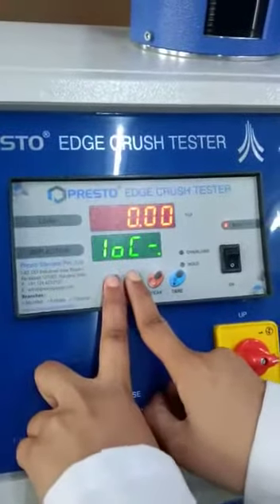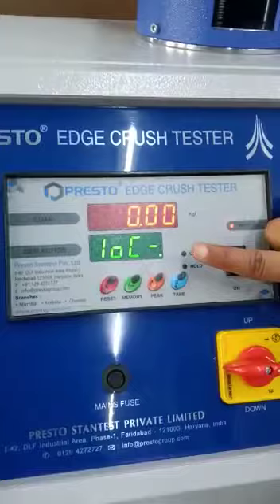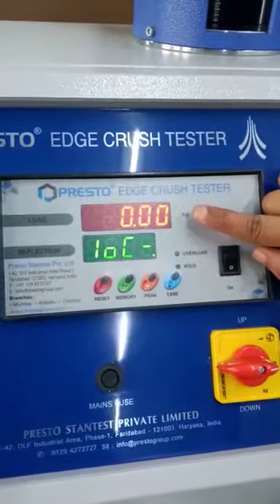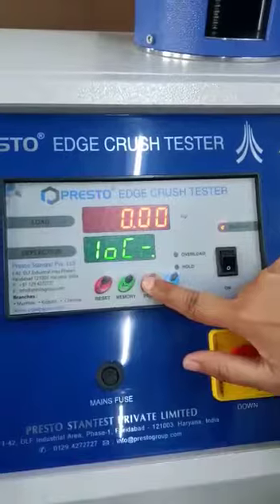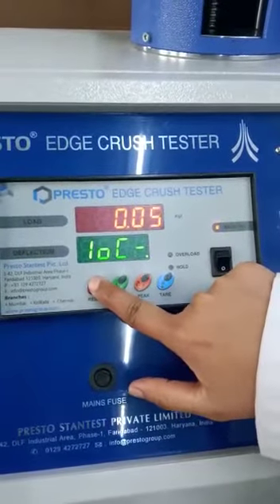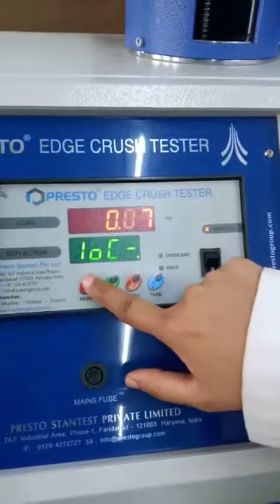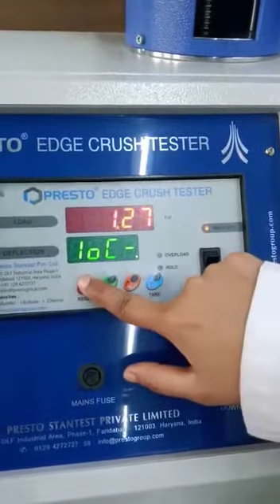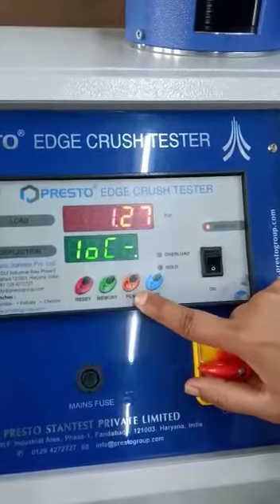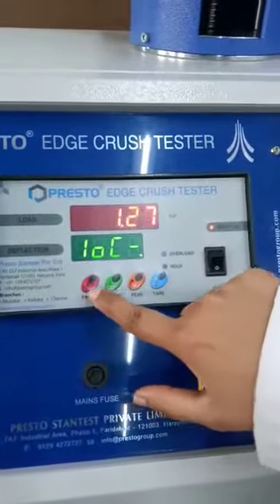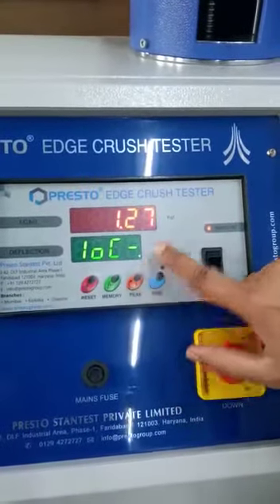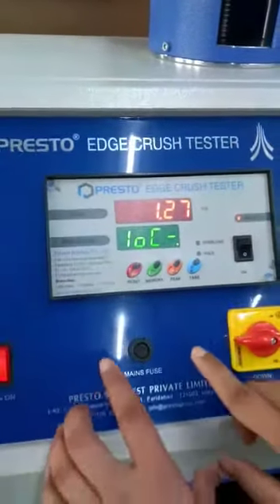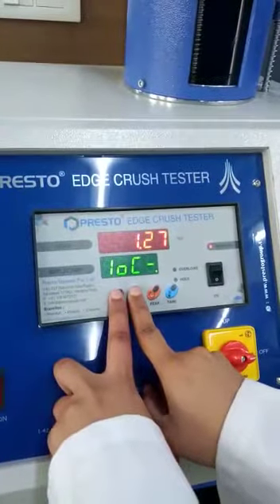So the first step: remove the weight, then press reset and memory together. It will show LOC, the lock value is 127. Press P key and enter 127 as password. For shifting, make use of the P key, and for increase and decrease use the reset and memory keys. 127. Then again press reset and memory.